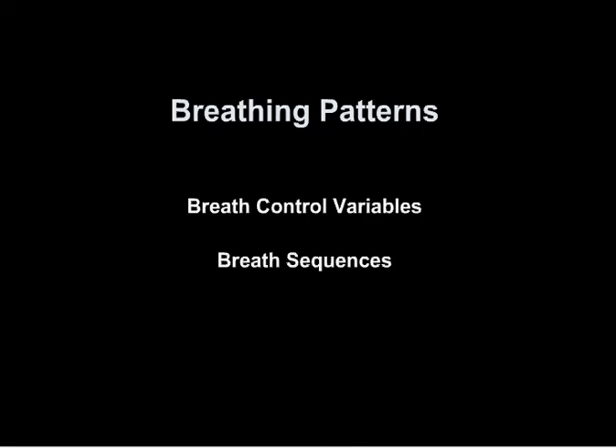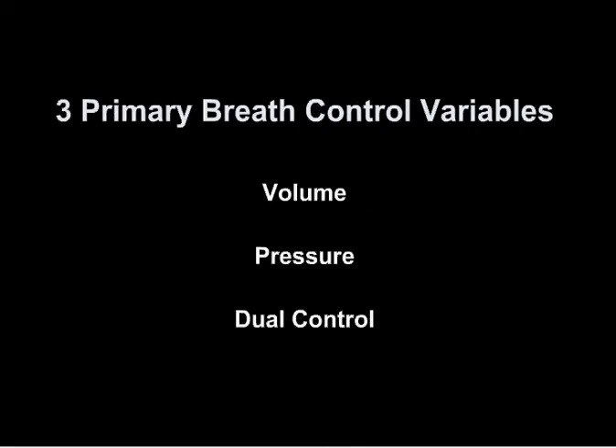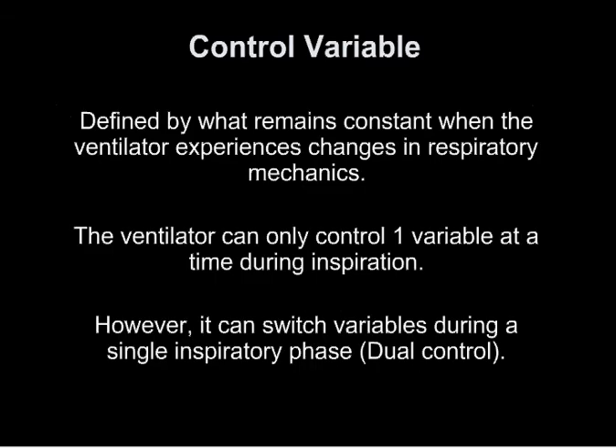There are three primary breath control variables: volume, pressure, and dual control. The control variable is defined by what remains constant when the ventilator experiences changes in the respiratory system. The ventilator can only control one variable at a time during inspiration; however, it can switch variables during a single inspiratory phase.